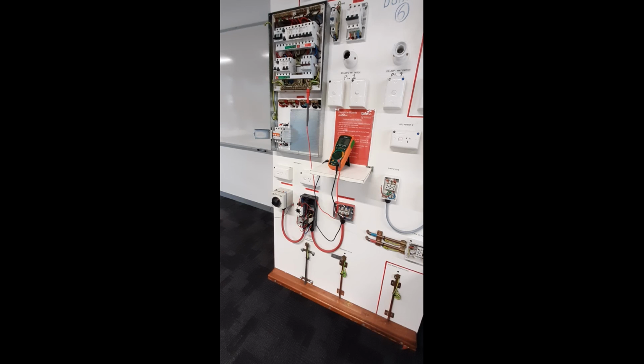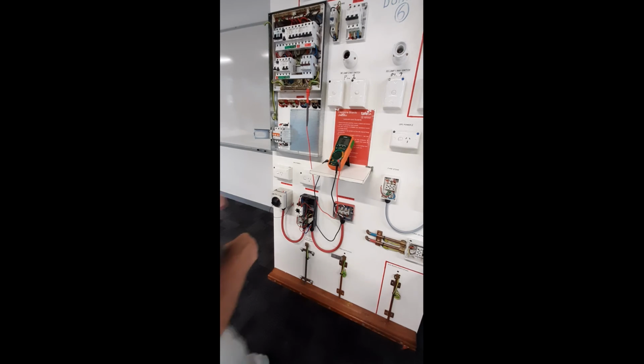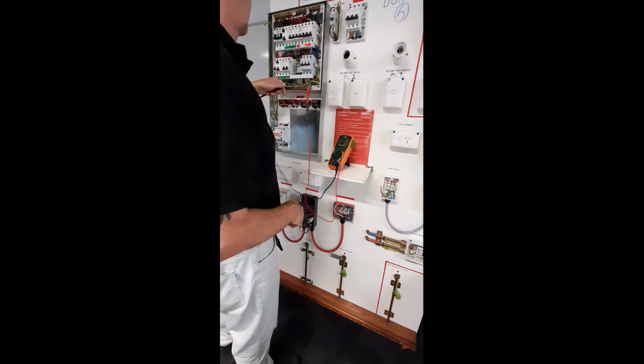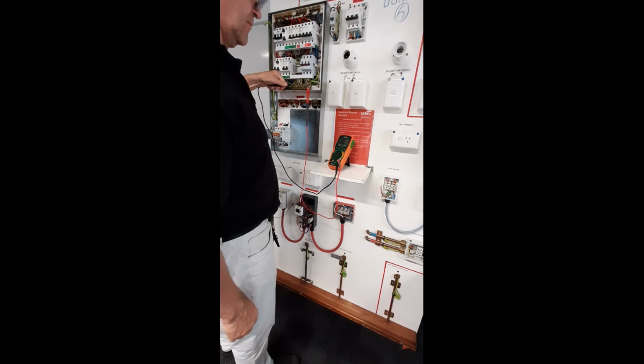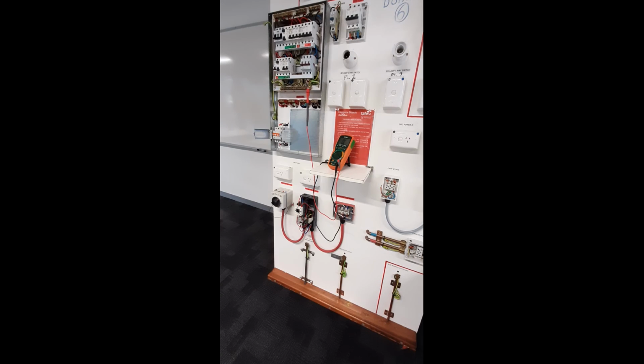Repeat the same tests for the earthing conductors. Infinity. You are now ready to conduct the verification of fault loop impedance testing of the electrical installation.